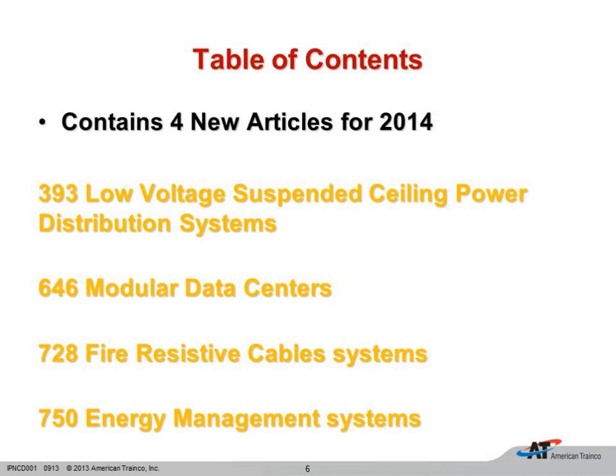So important that we do understand that. Now for our 4 new articles. Okay. Very first article titled Low Voltage Suspended Ceiling Power Distribution Systems. It is in Chapter 3, so this is a wiring method. And this gives us another opportunity to go ahead and, mostly this is going to be for lighting, but the ceiling grid itself will be the conductor. So I want to give you an idea that what this is going to be and the voltage range it's going to be in.